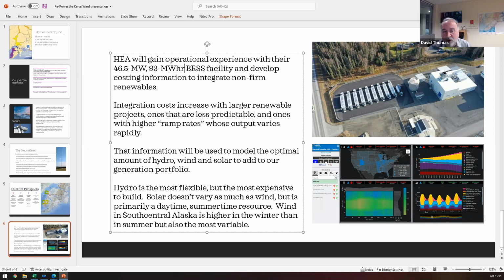So it got us through one dip in the wind, and it got us through the second dip, but can it get us through the third dip in the wind that hour? That's some of the modeling that we'll be doing: given the wind variability of a particular site, how much of that can we incorporate? Because frankly, I know a megawatt's fine, and I know 60 megawatts is too much. But where in there is that sweet spot, 10, 15, 20, 30 megawatts? That's a modeling effort we're undertaking now. So that ramp rate is one issue.